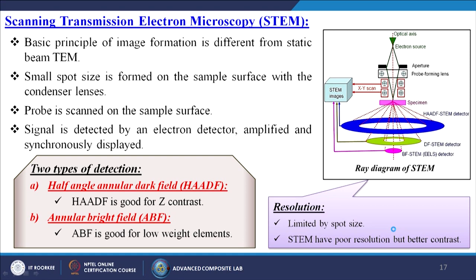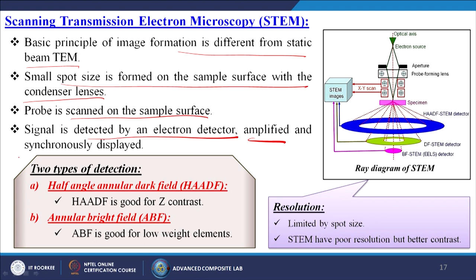Scanning transmission electron microscopy (STEM): the basic principle of image formation differs from static-beam TEM. A small spot size is formed on the sample surface with condenser lenses; the probe is scanned on the sample surface and the signal is detected by an electron detector, amplified, and synchronously displayed. Two detection modes: HAADF (half-angle annular dark field), good for Z-contrast, and ABF (annular bright field), good for low-weight elements. Resolution is limited by spot size, so STEM has poorer resolution but better contrast.